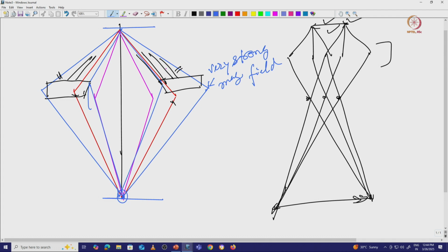So, using that aperture we are blocking lots of unwanted electron beam, and sometimes this helps us to increase the contrast. This is the function of the aperture, and this will be really helpful for biological samples.